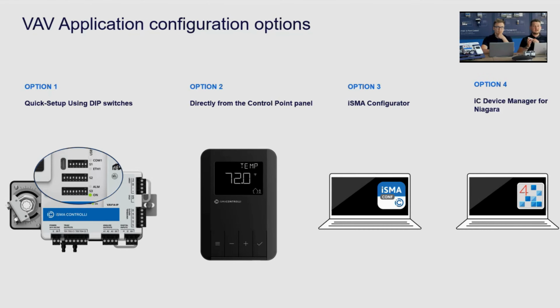So once you have the controller and the wall panel connected all together, there is an option to configure the application directly from the panel. The third option is our free of charge iSMA Configurator software. It is a portable free tool that you will install on your Windows laptop. And from the software, using the BACnet IP network, you can really easily configure the VAV either one-to-one or one-to-many. So we can configure and balance the whole VAV system.